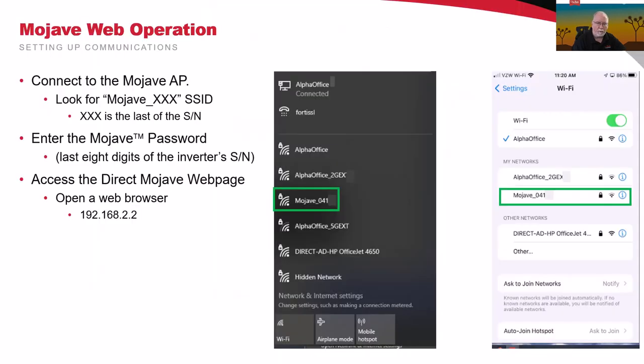So in order to connect to the web, you need to connect to the Mojave AP using whatever interface you're using. Look up the Mojave underscore and its last 3 digits of the serial number. Then enter in the Mojave, that'll be the last 8 digits of the inverter serial number. And again, to access the direct Mojave page, open up a web browser on the device and browse to 192.168.2.2.